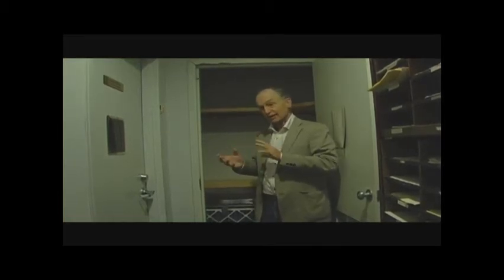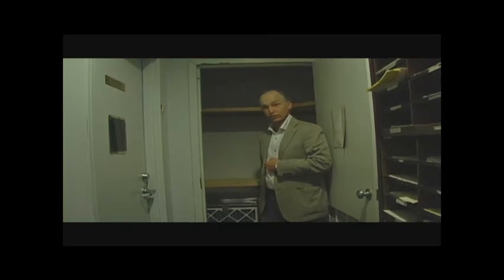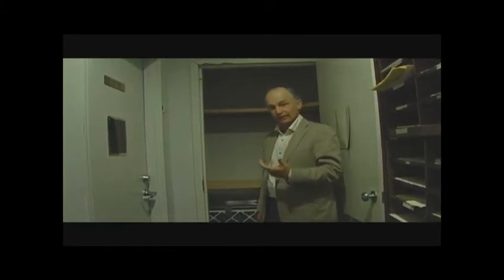When this happened, we reached another physics concept: dew point, or condensation. We increased the amount of moisture in the building, and this closet behind me — that's nice and clean and white — turned green with mold. The door behind you, which is a metal door, turned black with mold. So because we did not have an adequate return air path, not only did we lose comfort, not only did we lose energy, but we really affected the health of the occupants of this building.